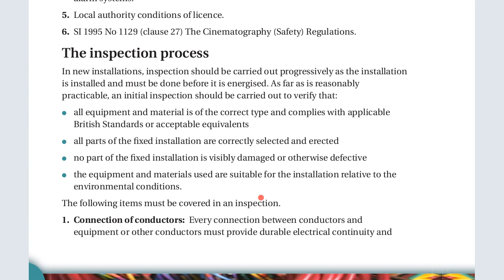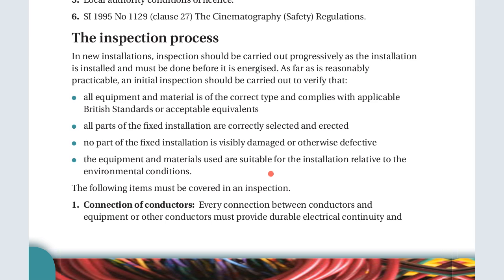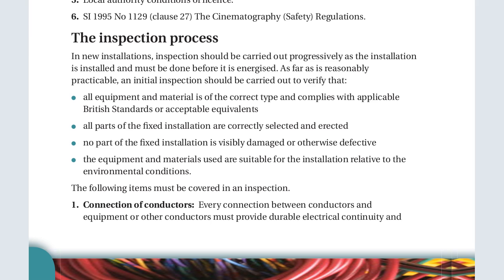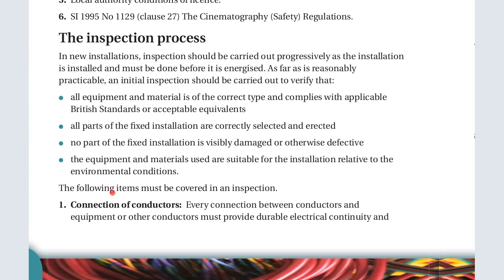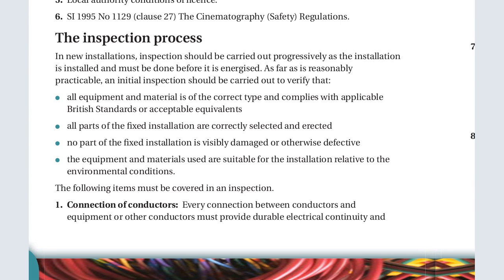As far as is reasonably practicable, an initial inspection should be carried out to verify that all equipment and material is of the correct type and complies with the applicable British Standards or applicable equivalents. So all parts of the fixed installation are correctly selected and erected. Another thing we check is that no part of the fixed installation is visibly damaged or otherwise defective, like if it is mechanically damaged, for example if something heavy was put on the wire and the insulation has been removed or peeled off. Another is that the equipment and materials used are suitable for the installation relative to the environmental conditions.